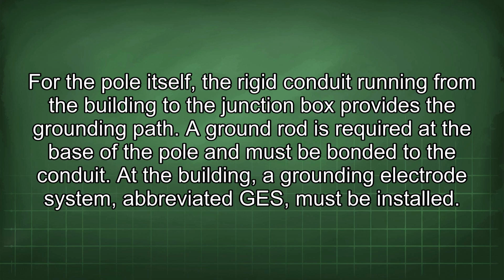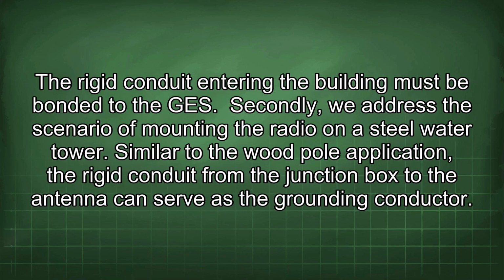A ground rod is required at the base of the pole and must be bonded to the conduit. At the building, a grounding electrode system, abbreviated GES, must be installed. The rigid conduit entering the building must be bonded to the GES.